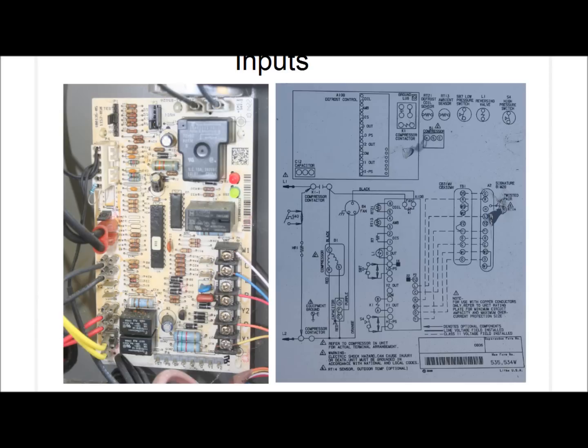We're using it because this is what you're going to be using most of the time anyway. Before we get started, I just want you to get used to talking about control wiring properly. A lot of new technicians always want to talk wire colors: yellow and orange and red and white and blue. And conveniently, we have yellow on a Y terminal, orange on the O terminal, red on the R terminal, and so on. If you need to call tech support or anyone to get some clarification on how things work, a lot of new technicians always want to say the red and the white and the orange, when they should be talking Y and O and R.